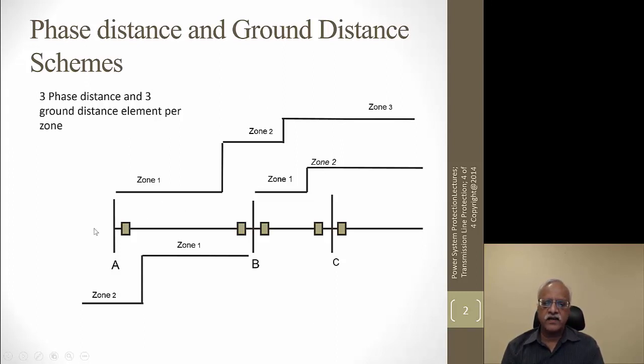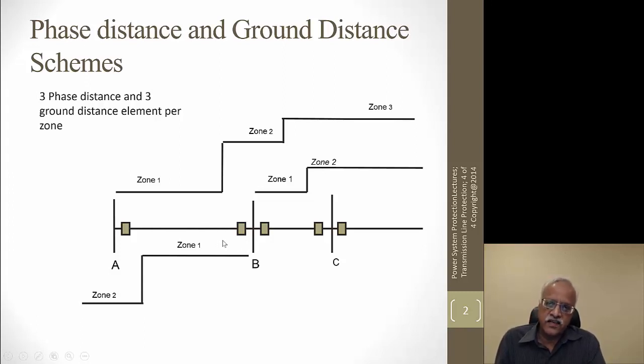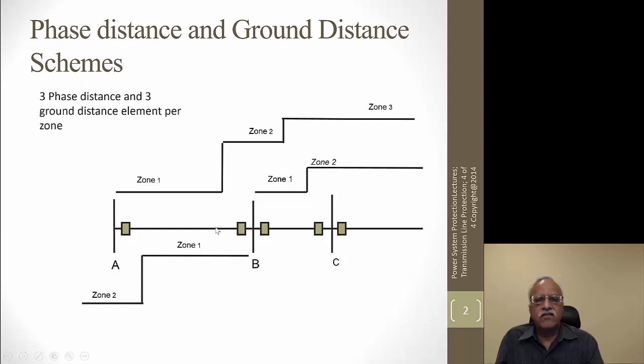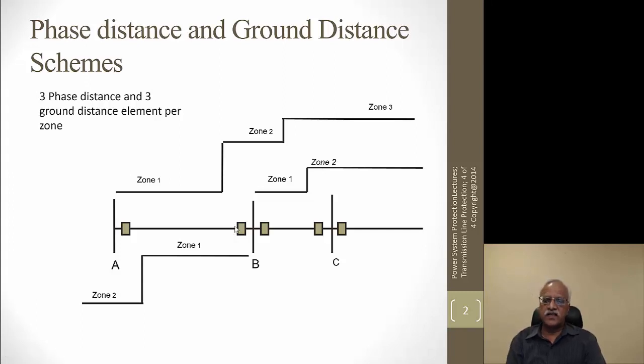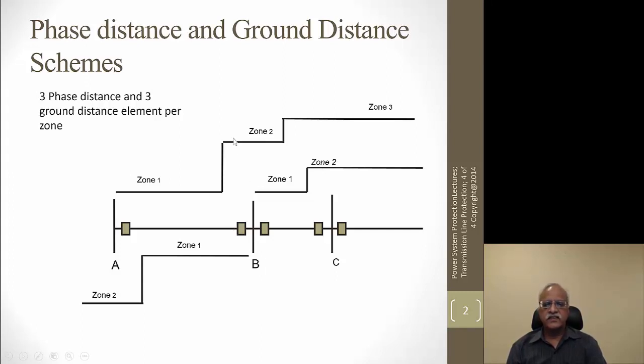We cannot measure 100% of the line section instantaneously to make a decision, because due to CT and PT errors, relay design errors, and line parameter errors, we can be sure only if the measured impedance is about 80% to 85% of the actual line impedance between line section A and B, and we allow the relay to trip instantaneously. If the fault is in the last 15% of the line section, we are not sure whether it is in line AB towards end B or in line section BC very close to B. So to make this differentiation, we provide a time delay — zone 2 distance relay, phase distance relay, and ground distance relay.